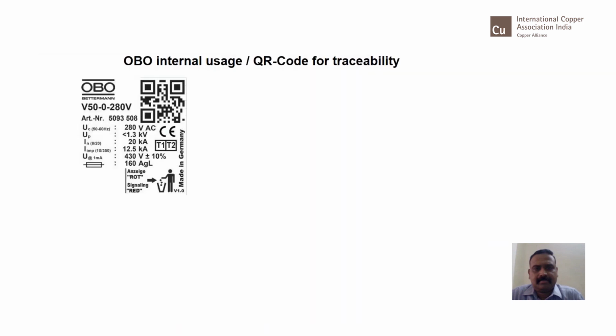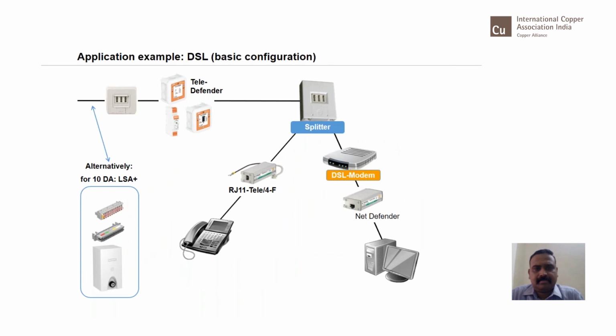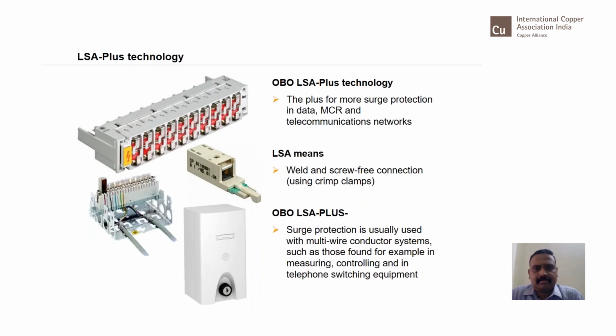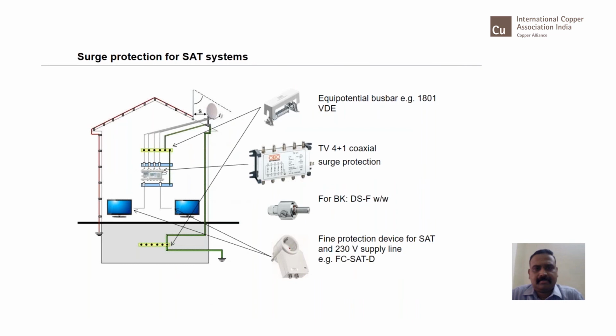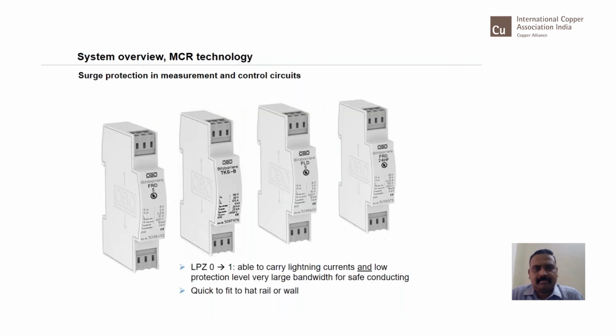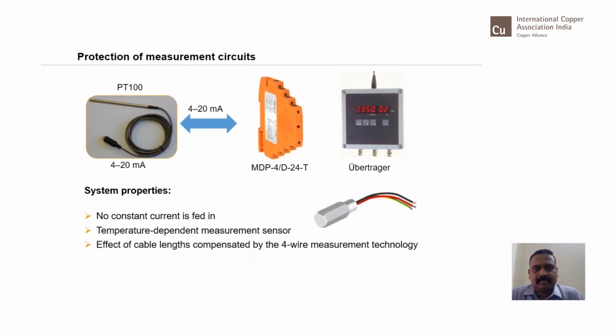You have surge protection devices for power. You have surge protection for data, which can be used for routers and modems. You can use it for EPABX systems where the telephone lines come from outside. You can use it for dish antenna and televisions, which are more costly, to protect against surges from the coaxial lines. You can use it for 4 to 20 milliamperes receivers as well as transmitters, both on the field side and the DCS SCADA side.